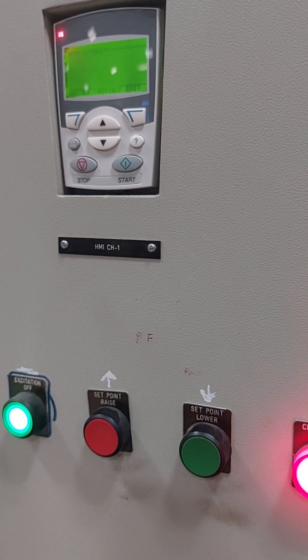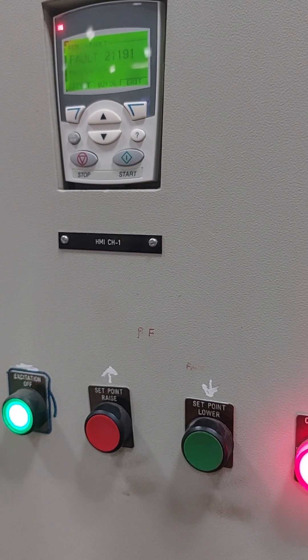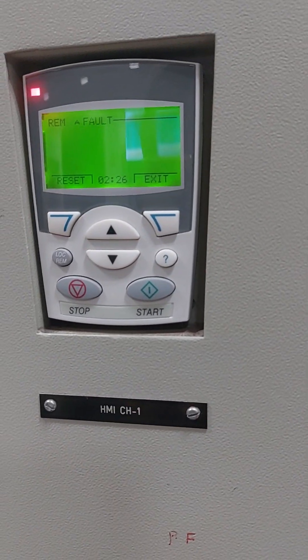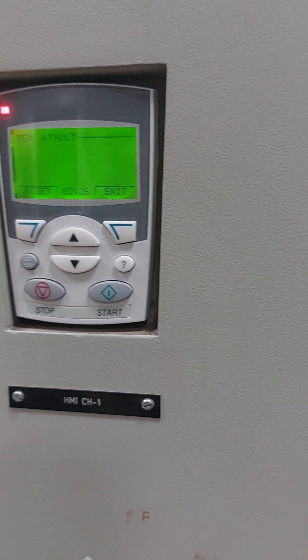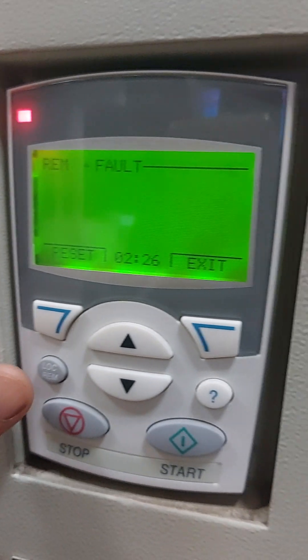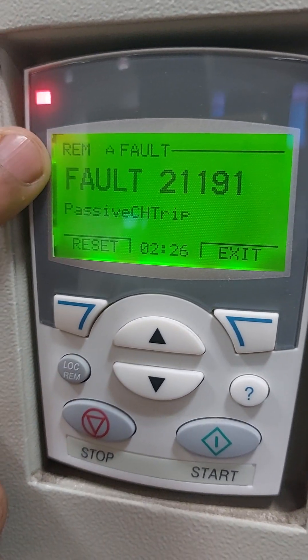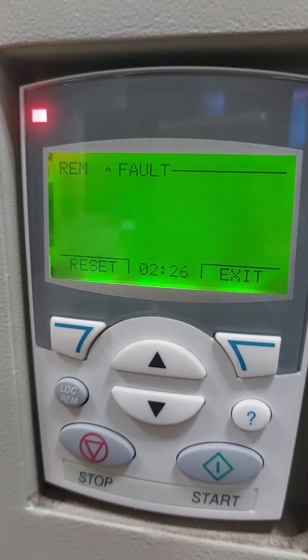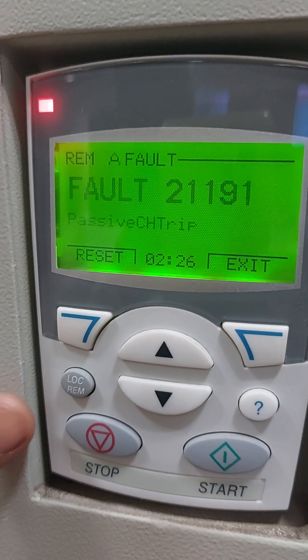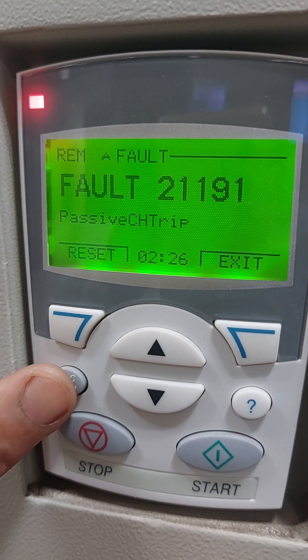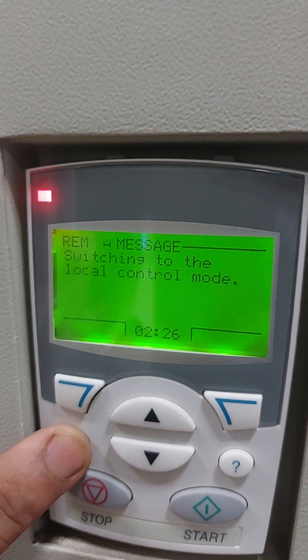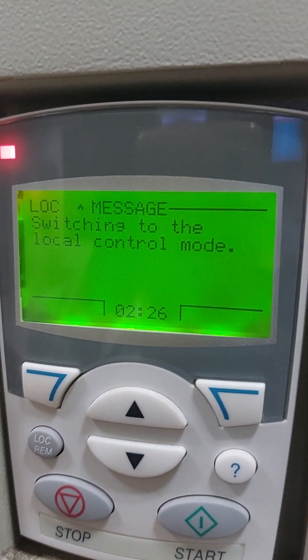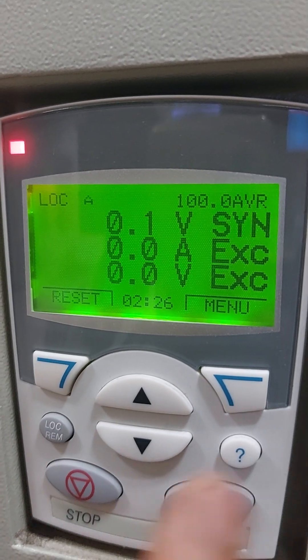So before giving the excitation, here this is the HMI. This model is AVR Unitrol 6080. First, we have to make it in local mode. Presently REM means it is in remote mode. So whatever changes are required, we have to make it in local mode. So if you press it for a few seconds, automatically it will change to local mode. LOC means local mode.